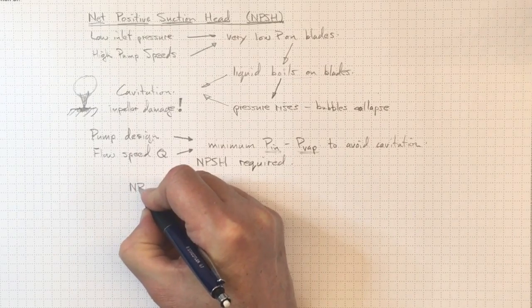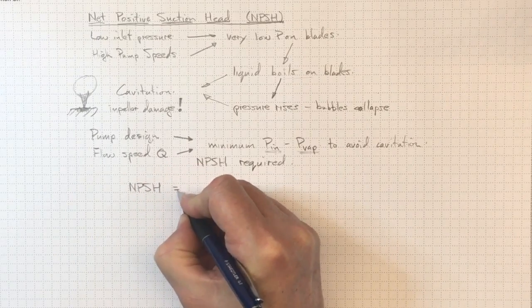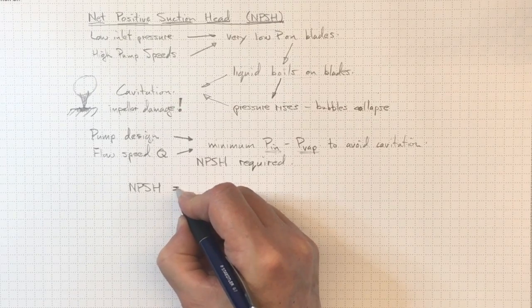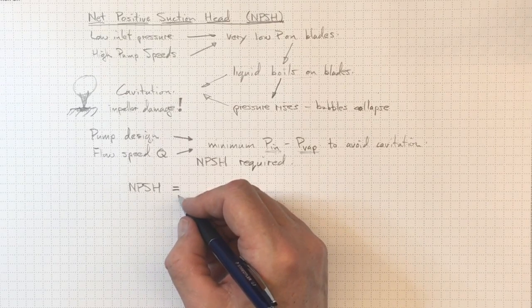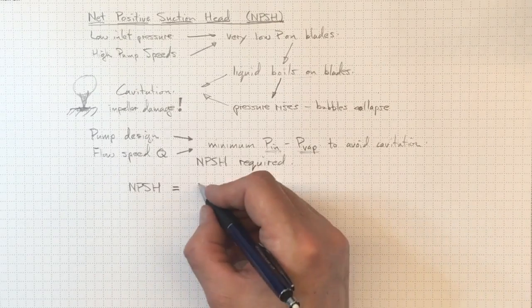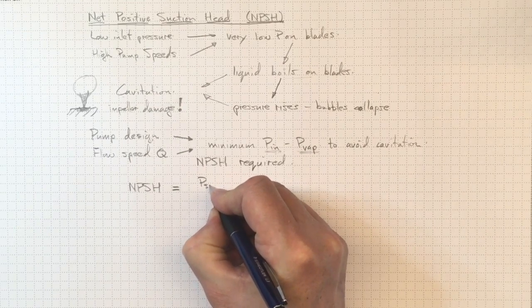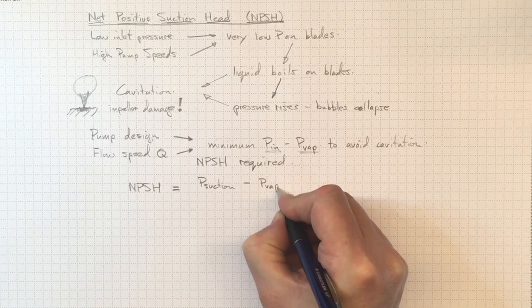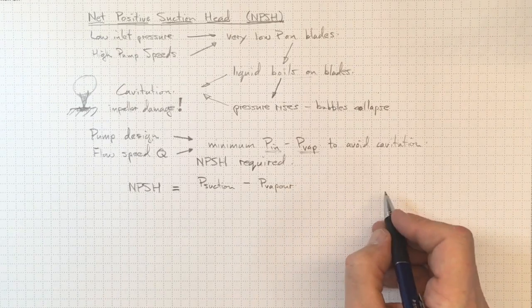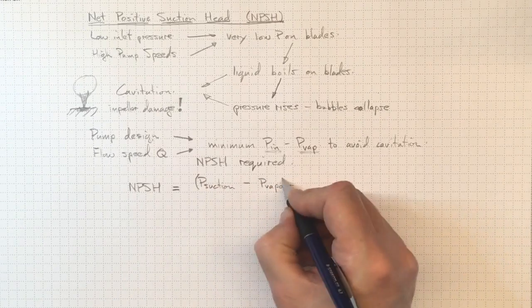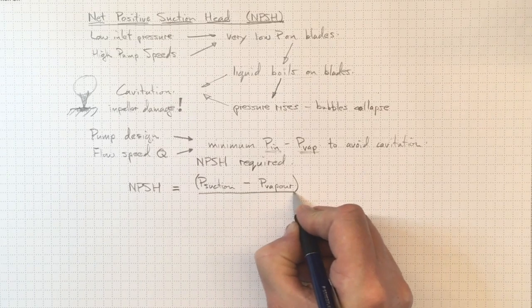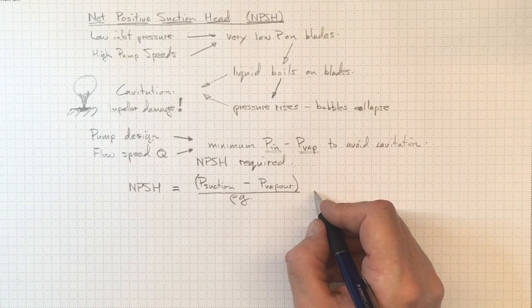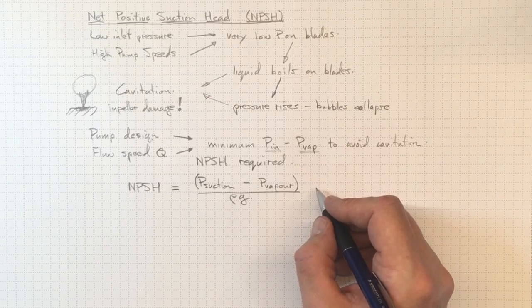Now the net positive suction head is put in terms of head or elevation, increase in height, for the same reasons that we're using head for all of our pump calculations. It's just the pressure in the suction of the pump minus the vapor pressure for the fluid at that particular temperature divided by rho g to put it in terms of head instead of in terms of pressure. Now let's look at how we calculate this.